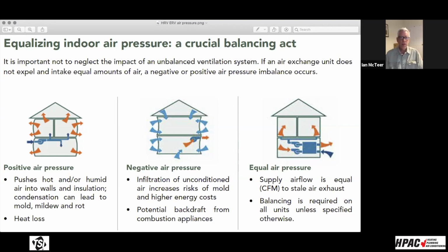But the main issue I have is that I have a modulating gas furnace that works on a communicating system, and it doesn't talk to my HRV. So there's no way to interlock the two devices without just allowing the furnace fan to run all the time, which is okay because I have a better air filtration system too. So I'm going to run the fan all the time anyway. But I think for the average consumer, I'm not sure that they want to do that.